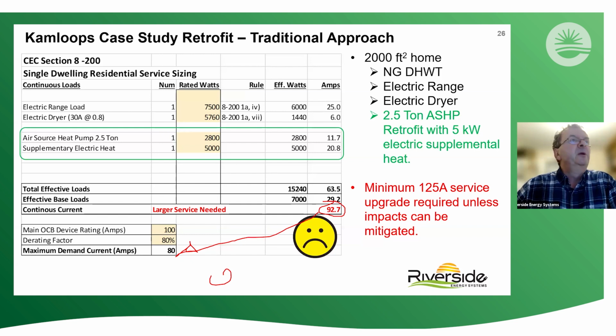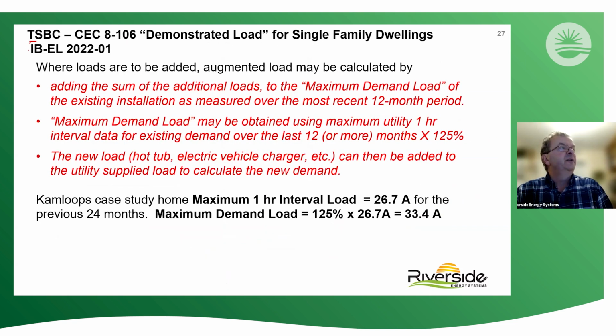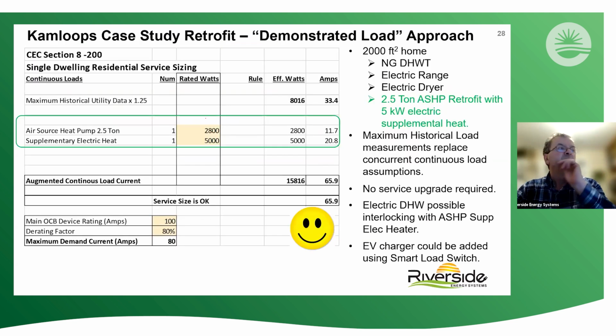But if we dig a little deeper and we apply the Technical Safety BC bulletin that shows how to use the demonstrated load information in BC, Technical Safety BC says if we take our maximum demand load, which in my case was 26.7 amps, and we multiply it by 125%, we'll get a maximum demand load projection that we can use as a demonstrated load to get our augmented load, it's called. So doing so, using the historical data and my maximum demand uprated to 33.4 amps, I can put in that heat pump with the boost heat and have plenty of margin left, and there's a happy ending, no service upgrade required.